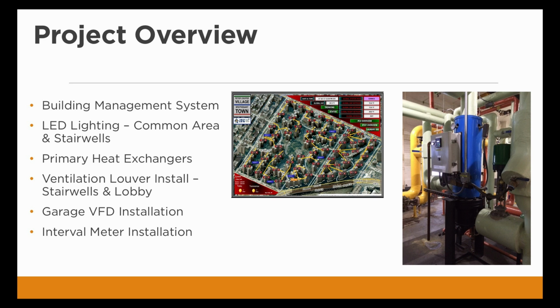The primary heat exchangers were an end-of-life replacement, but it allowed us to look at different ways to control things — there's so much good stuff out there nowadays. We ended up putting electronic actuators on the incoming steam for the heaters, and installed preheat exchangers so we could preheat the water before it goes into the heat exchanger, saving hundreds of M-pounds of steam in the process.